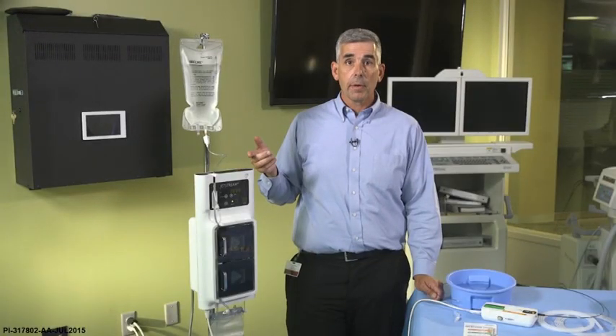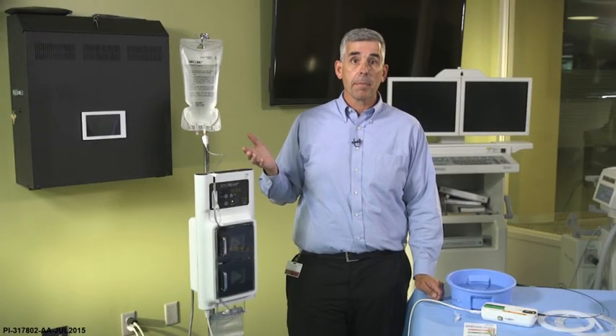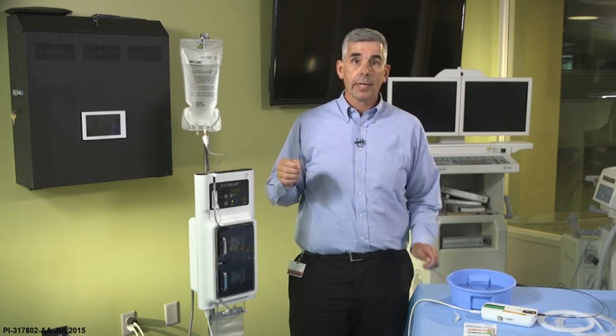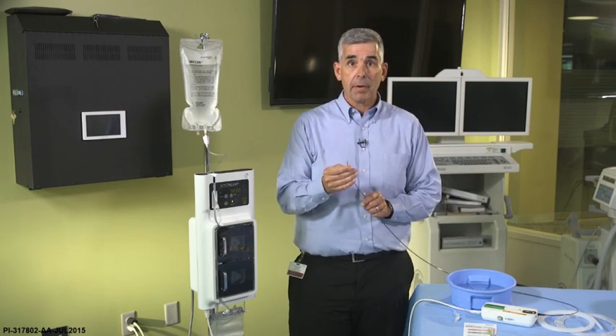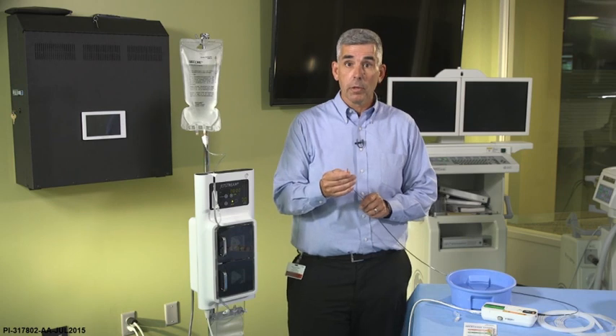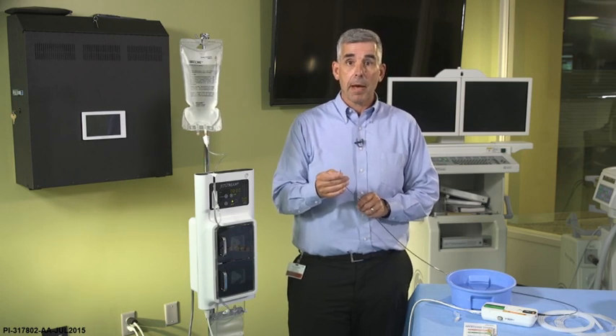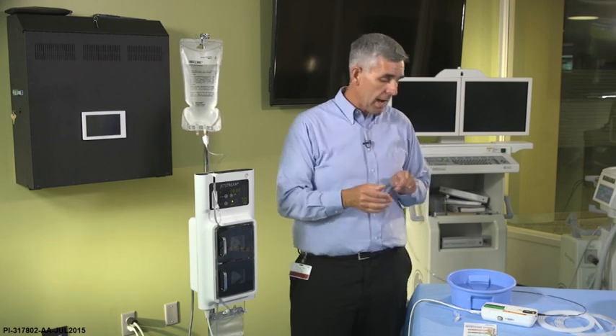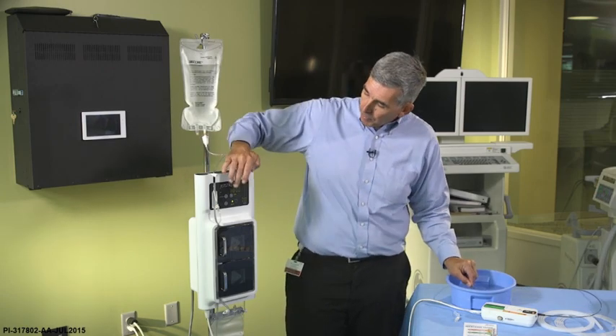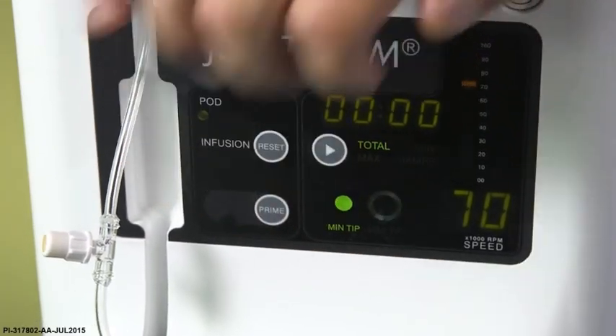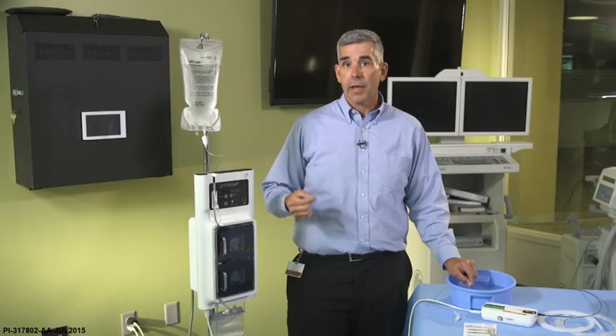With the catheter loaded, priming is necessary and the next step before using the catheter. We're going to instruct the sterile person to place the tip of the Jetstream catheter in a sterile bowl and keep away from the sides and the bottom of the bowl during priming. Have the non-sterile person depress the prime button. You'll hear the catheter start to prime. The priming of the catheter roughly takes 70 seconds, and the machine will beep to let you know when the prime is complete.